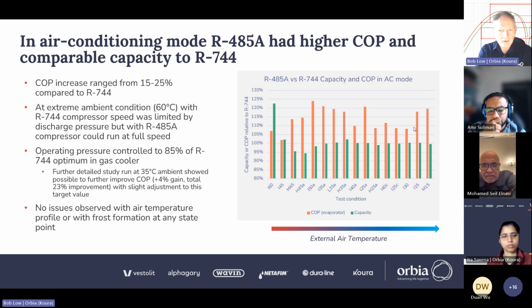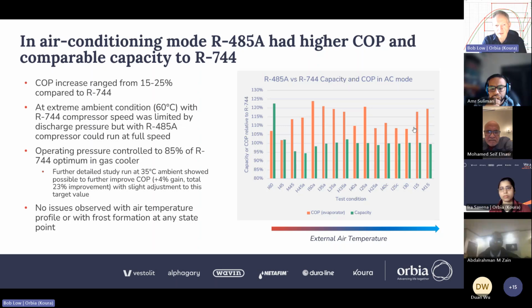And what we found was we'd basically used a heuristic to use 85% of the optimal CO2 pressure at each state point, and that gave those results. We found if we then did a more detailed COP optimization study at 35C, we could squeeze another 4% out of the performance. So we could lift that point up from 19% COP gain to 23% COP gain, just by moving a couple of bar on the exit temperature.